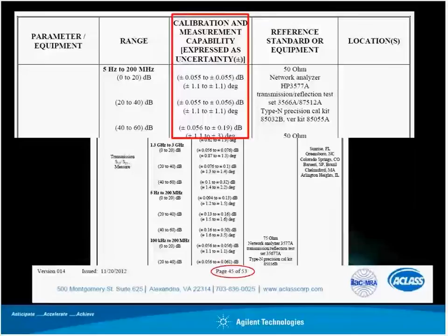And the calibration and measurement capability of the laboratory is the parameter that the laboratory is calibrating to, the range, the expressed uncertainty, the reference standard used for the calibration, and in this example here, the locations at which the calibrations are taking place. But looking at the scope, there's a couple areas that we really need to focus on to make sure that the laboratories have the capabilities to perform the calibrations.